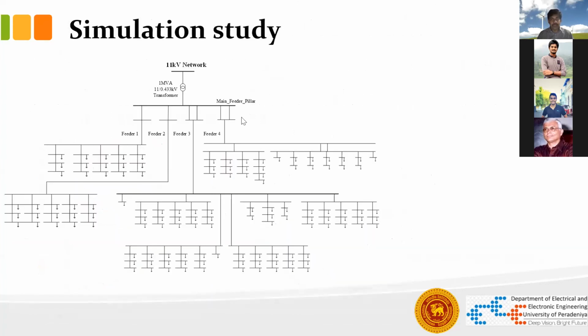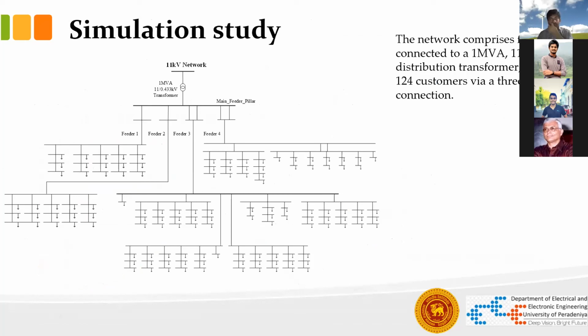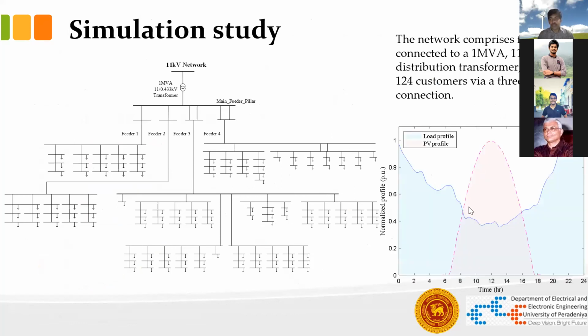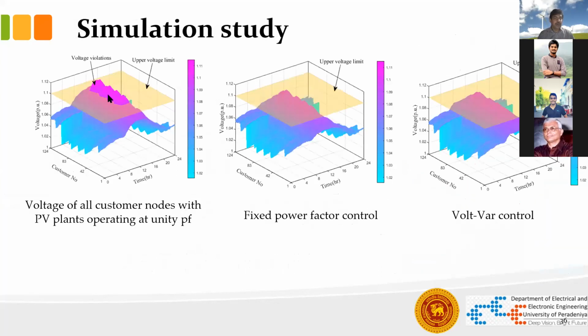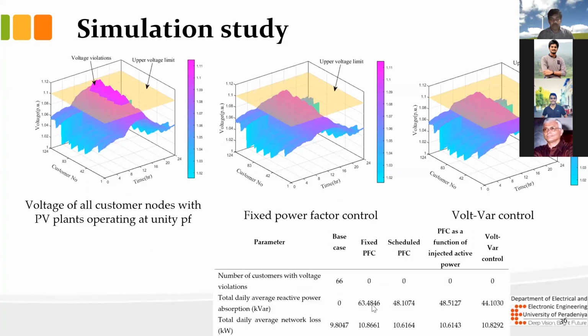And you can see some simulations we did in a Malaysian network, which has 120 consumers connected via 11 kV to 0.433 kV transformer, 1 MVA. The load profile is given in blue, and the solar generation within the network is given by this dotted purple area. And you can see that without any voltage control, some of the customers will see the voltage above the statutory limit during the day, midday. Whereas you can use fixed power factor control or the volt-var control to bring the voltages below the statutory limit. And you can see from here how each method performs.